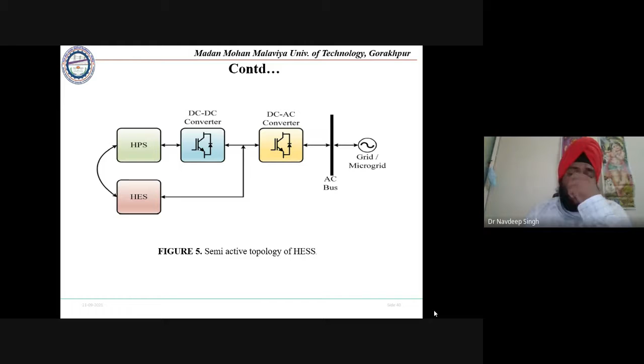The peak power requirement of the system is satisfied by the HPS, a passive device. Power is not controllable because there is no controller. A controllable device is there, but in this case, voltage is controlled through a DC to DC converter, and power is again not controlled because the energy storage is directly connected to the common bus of the system. Semi-active topology with controlled SC and controlled battery has been analyzed. The power converter of the supercapacitor is oversized to handle the pulse power output.